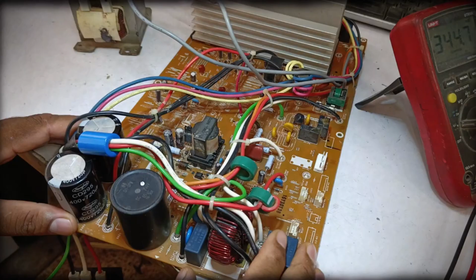This is a Panasonic outdoor PCB, and it's completely dead, not turning on at all. Here's the situation: when the customer had it installed, the electrical polarity was connected incorrectly by a technician. Due to this, the PCB stopped working within a week. I've identified part of the issue, but I'll explain the troubleshooting method step by step.